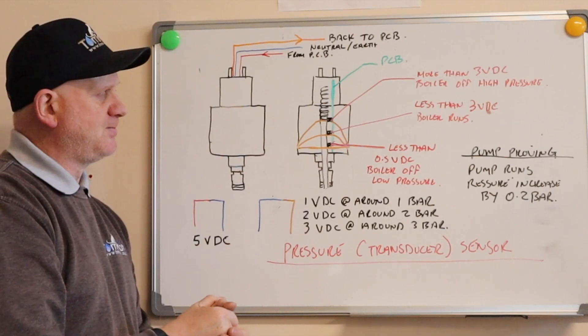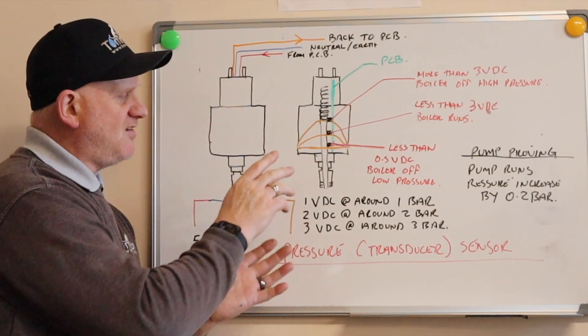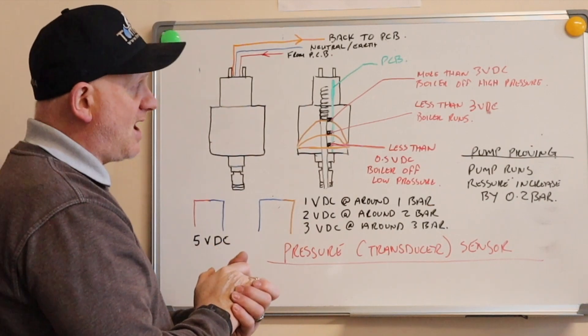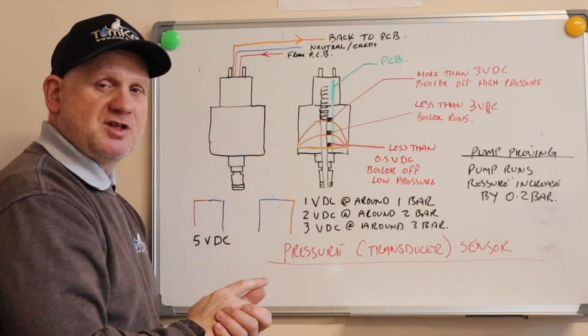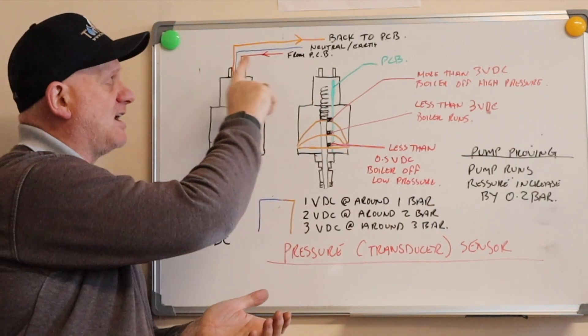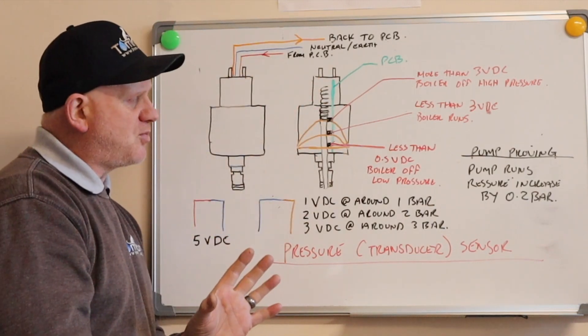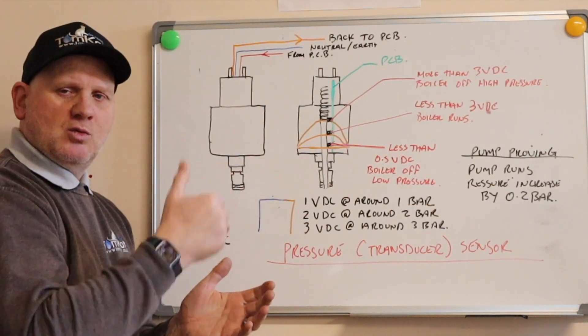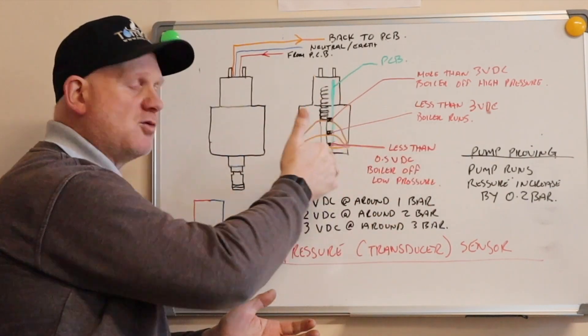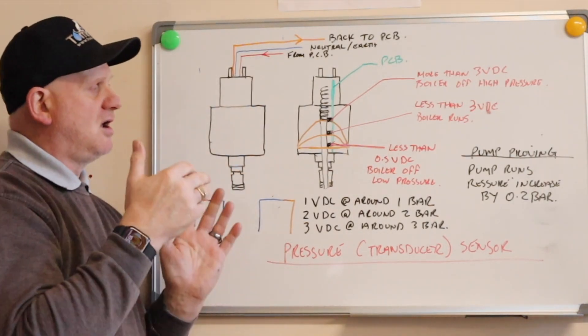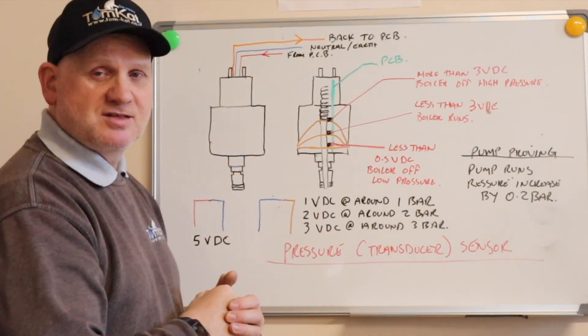But if the pressure goes over 3 bar, then the boiler will turn off because it will be getting 3 volts DC back down the orange and it'll know there's a problem. And also your pressure relief valve will activate, and then this will put it down into a fault and stop the boiler working and won't work again until you press the reset button once you've put the water in there.